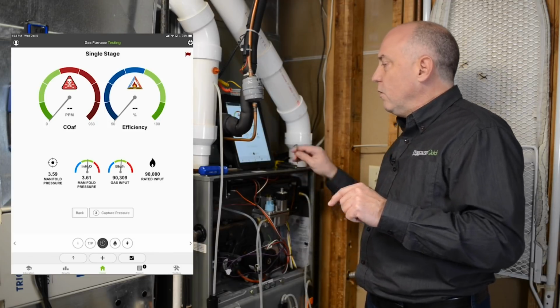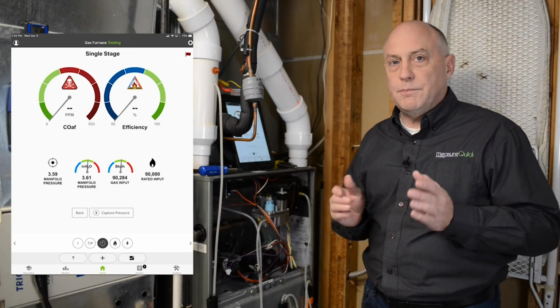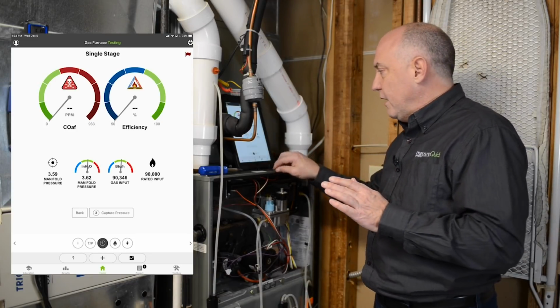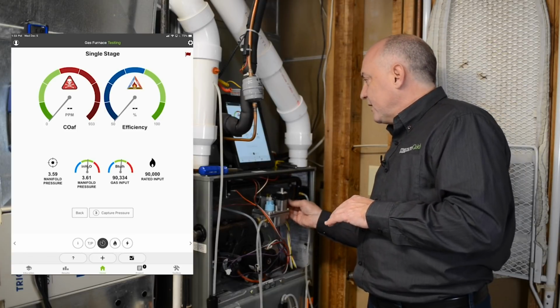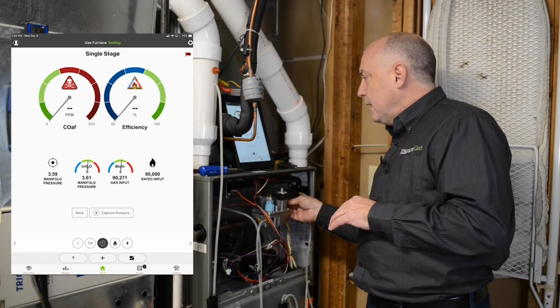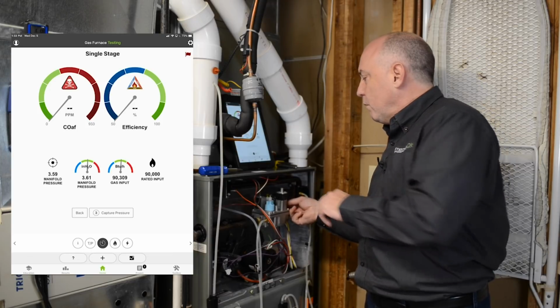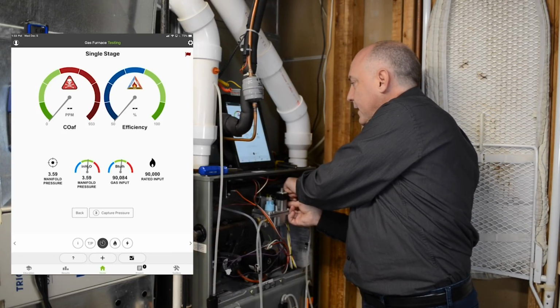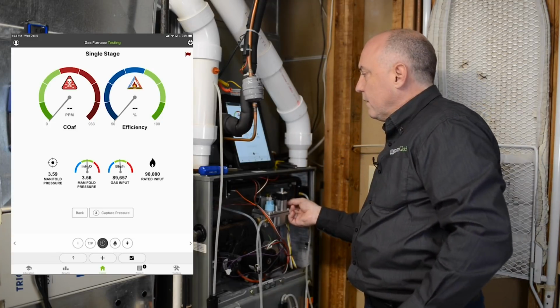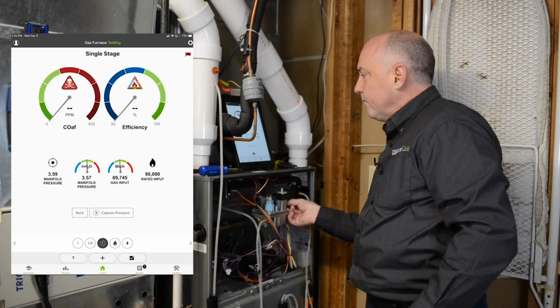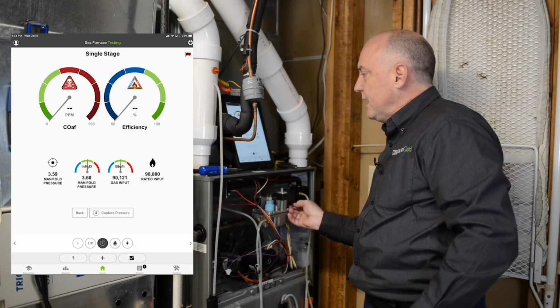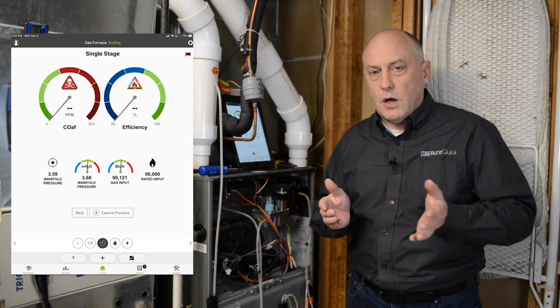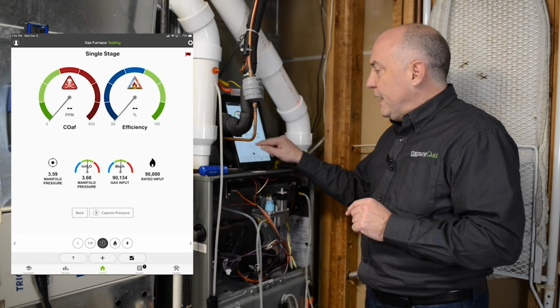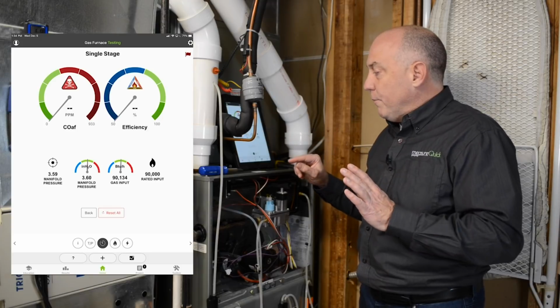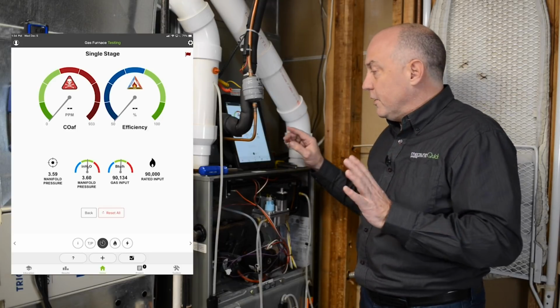So 3.60, we're at 90,246 BTUs, well within the range there. We might tweak that just a little bit. The regulator's got to settle in just a hair, so they do require some fine adjustments, but we're well within where I want to be. I just like setting it up as exact as I can. That's just me. So 3.57. Why do you do this? Because you can, right? 3.59 inches of water column, so now we're spot on there. Now I'm going to hit capture the pressure here. You can see I have my manifold pressure good. All my pressures are spot on, so I'm ready to go.